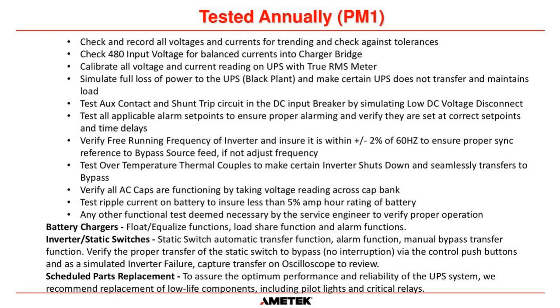We check thermal couples to make sure they shut down the system as they should if there was an over temperature occurrence. We verify the AC caps are functioning. We test ripple current on the battery, and we check that it's less than 5% of the amp hour rating of the battery. And then we do any other functional test deemed necessary by the service engineer. And for the inverter static switch, every single one of our FSEs also carry an oscilloscope. What we do is we capture the transfers between inverter to bypass on the static switch and bypass back to inverter. And in the annual PM, we will replace any components that have a low life. That includes pilot lights if they are incandescent and the critical relays that I mentioned earlier.